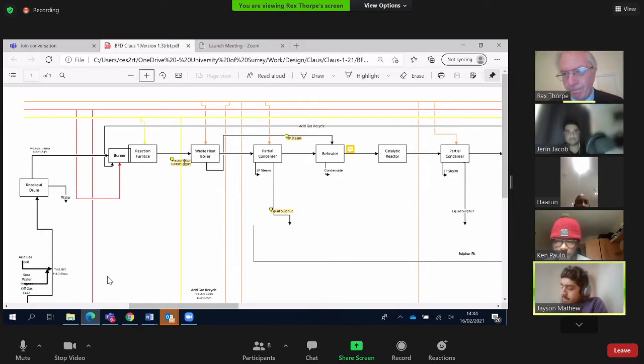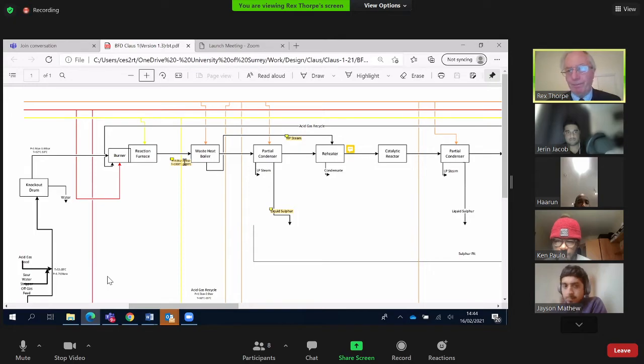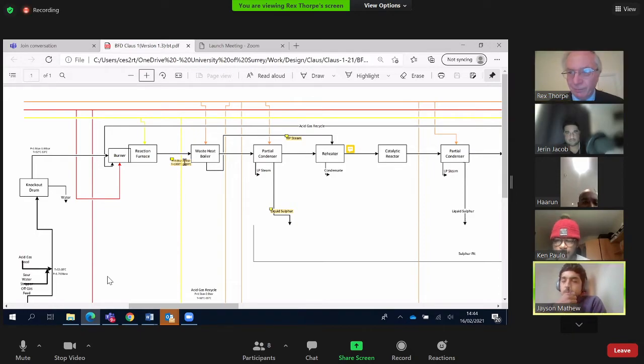Okay, so how did the pressure go up? Well, the answer is it can't. The only way you can increase the pressure in a continuously flowing process is to use a pump or a compressor. This is a gas, so you can't use a pump. And this is a gas with hydrogen sulfide in it, so you can't use a compressor. So the pressure can't do that.